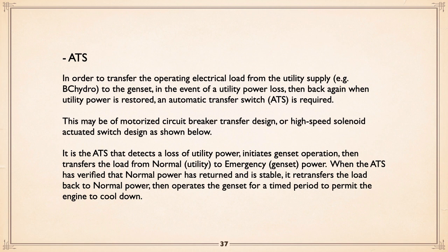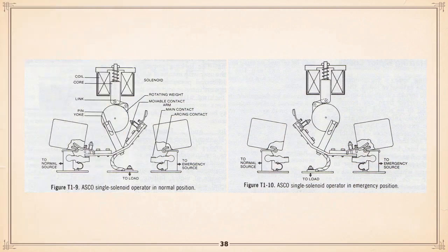The other approach is to use a high-speed solenoid actuated switch design, and I'll show that in just a second. And I'll make the comment, who's the manufacturer? I'll mention names. ASCO is by far the one that does this best. I've seen GE do it. We had problems with GE. Would I deal with them again? No. ASCO's always been very good with the switches. And in a few cases where I have allowed somebody else to bid afterwards, I wish I hadn't.